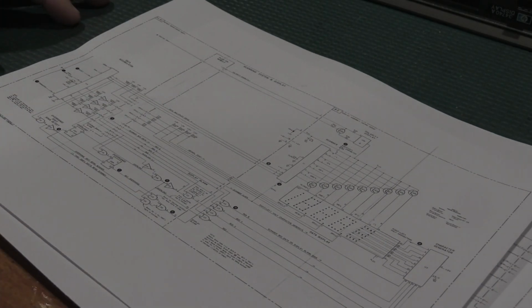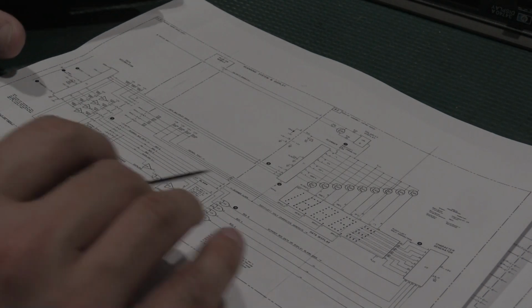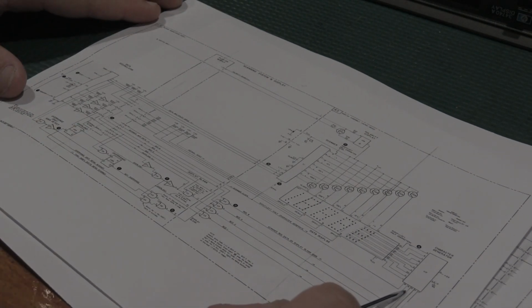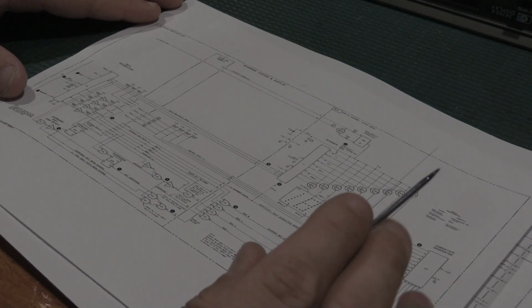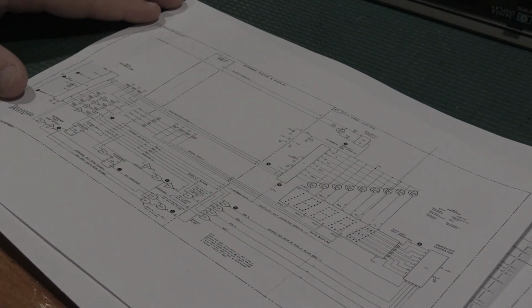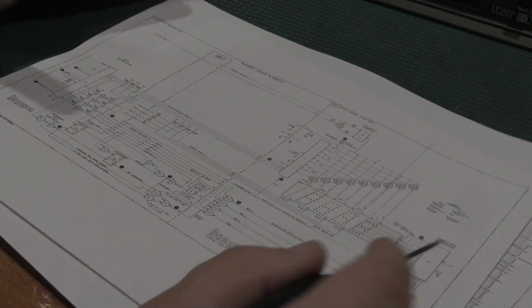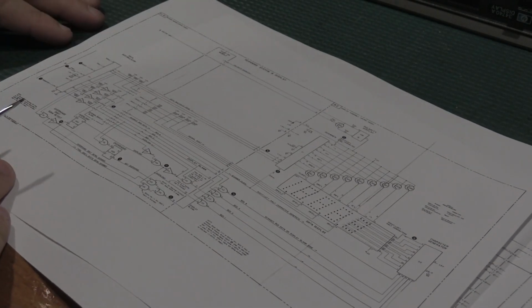U2 did not come out well. That was not the fault of the unit or anything like that. I'm pretty sure that was a technician error in getting that out, and especially with it being a ceramic package, it was not easy to desolder and came out poorly, which is how we had to swap displays and finish the repair to get a functioning meter.